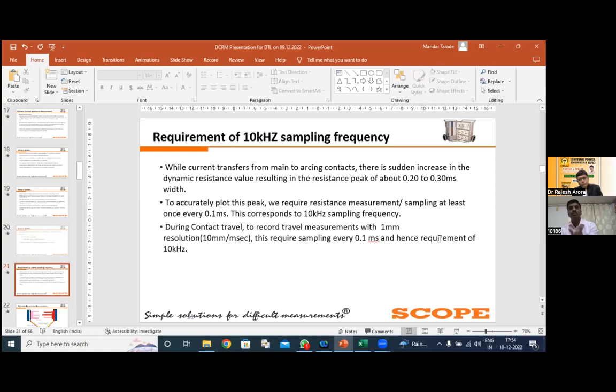T is equal to simply 1 by F. So if you do T equal to 1 divided by 10K, it will give you a step resolution or step size of 0.1 millisecond. With the help of this you are able to capture the drastic change in the resistance, or the change in the signatures, during the transition from the main contact to the arcing contacts. That's why the 10 kilohertz sampling speed is very important.